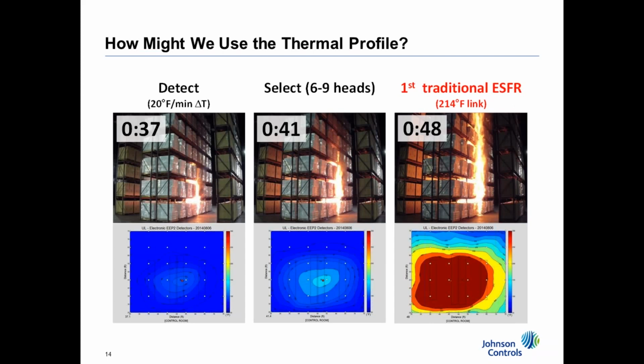And where this really shows up, and it's very interesting, is if you look at the thermal profile in the far left-hand picture. In 37 seconds, you can see you have very little red inside of all that dark blue. This is done through thermal imaging. If you take that 37 seconds and go to the extreme for a traditional sprinkler at 48 seconds, you look at the heat release difference when you're dealing with these exposed expanded plastics. In our application, we're going to be activating, in almost every case, 9 sprinklers through electronics and the panel writing process. You're going to be at about 41 seconds, still well within the heat release that you're trying to pick up.